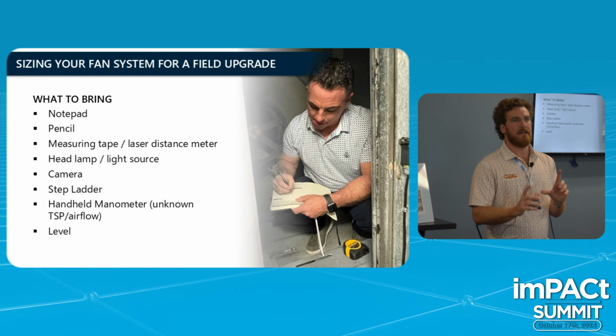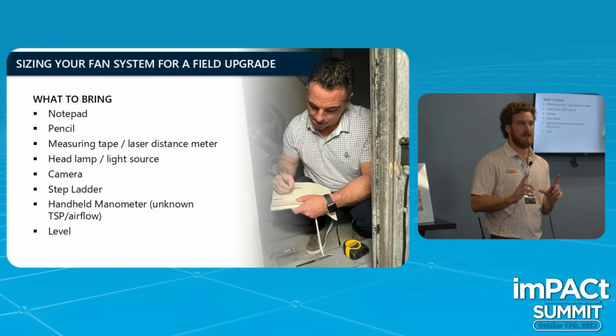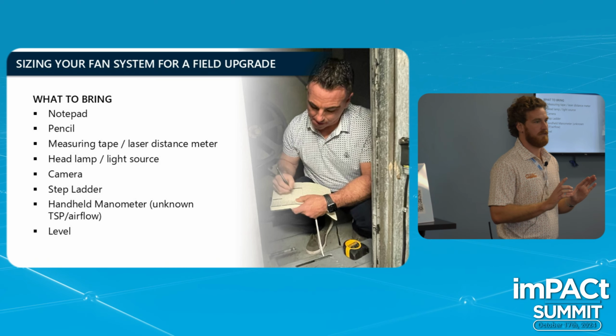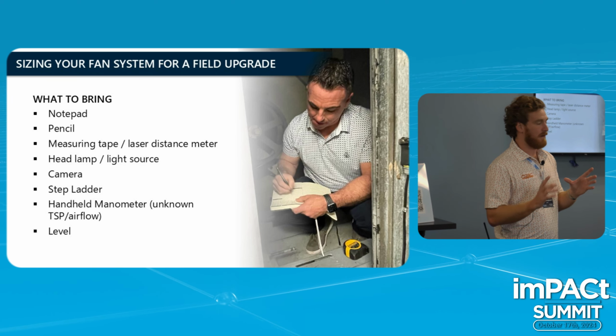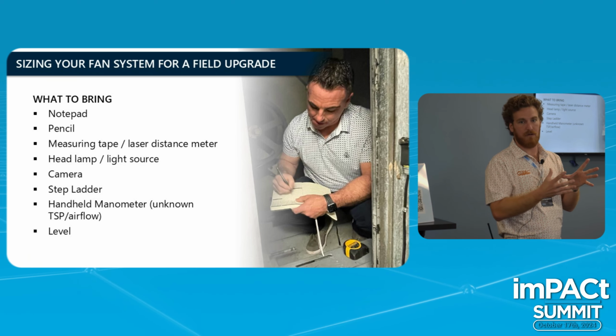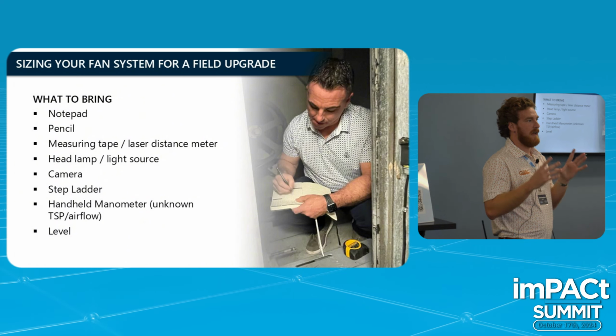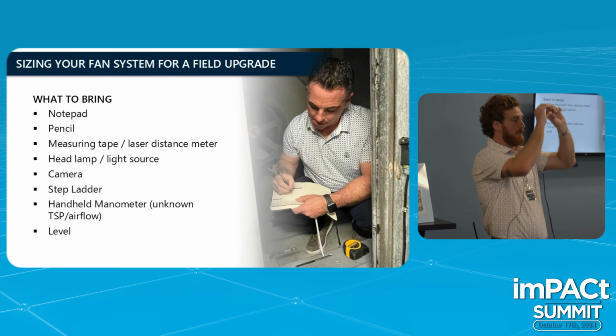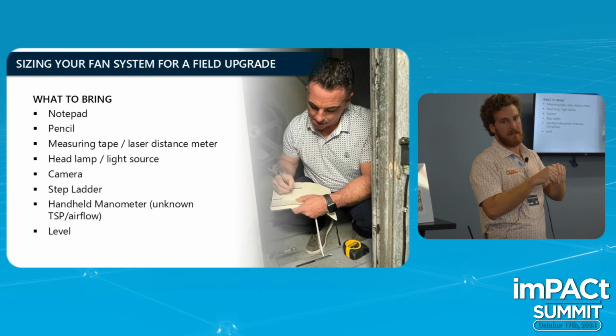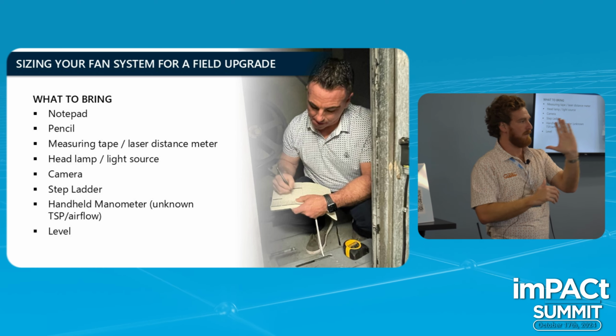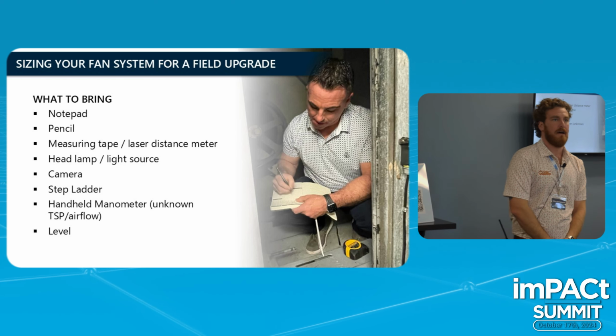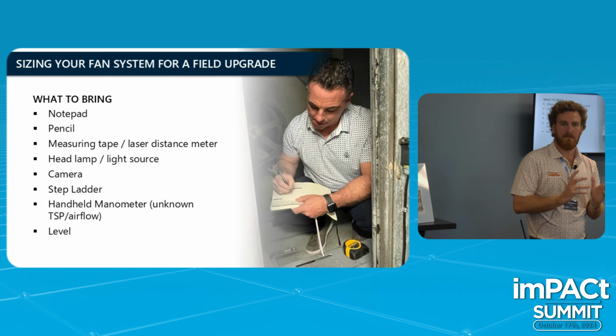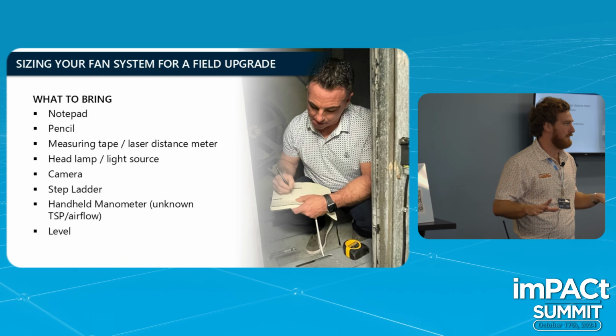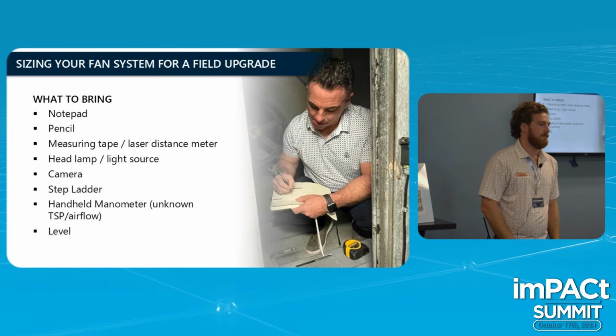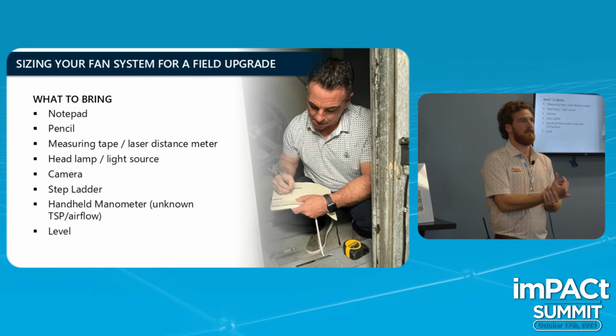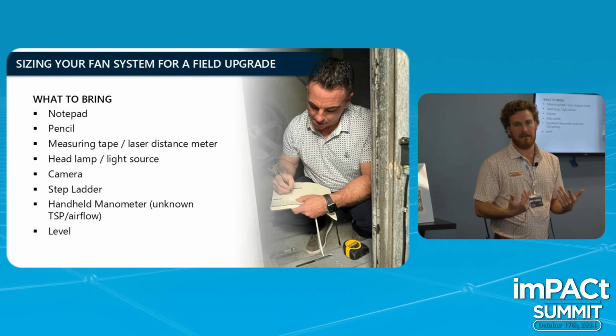The internal height and width of the system is really what you want to focus on, because if it's a regular air handling unit with a solid metal enclosure, you just give us those internal dimensions and we'll mount the perimeter angle inside the unit and fit each panel through. Getting those dimensions correct is important for the product to fit without extra sheet metal work. It's usually better to oversize the width and height than to undersize it.